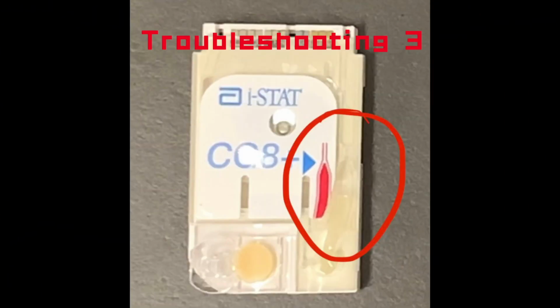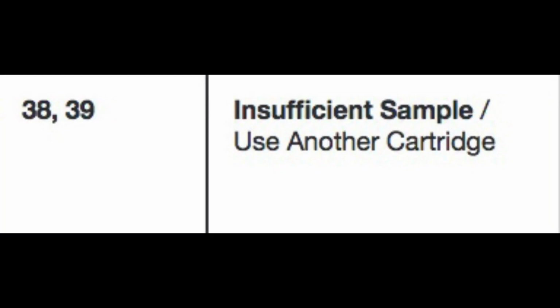Now for the next issue, we're going to demonstrate what happens if you put an insufficient volume of sample into the capillary area. When this occurs, it will show error code 38 or 39, indicating there is not enough sample in the sample well. This is a common error, so ensure using proper pipetting technique and always check if the capillary area has an adequate volume of sample.